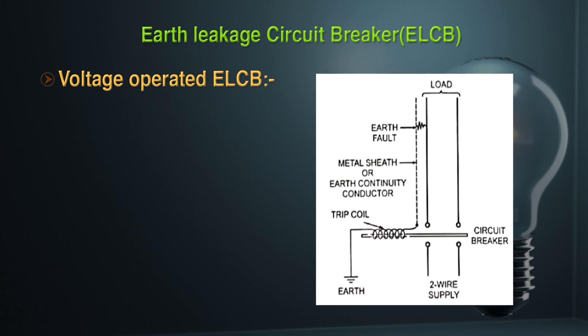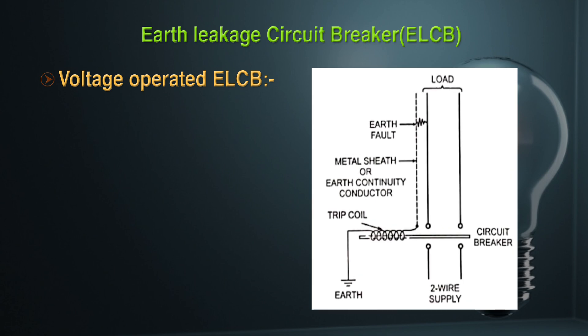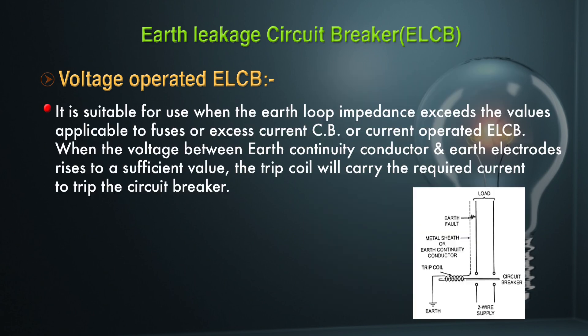The voltage operated ELCB is suitable for use when earth loop impedance exceeds the value applicable to fuses, excess current circuit breakers, or current operated ELCBs. When the voltage between the earth continuity conductor and earth electrode rises sufficiently, the trip coil carries the required current and trips the circuit.